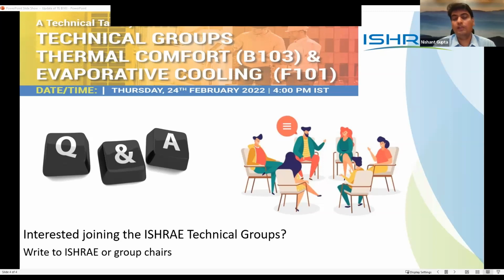Once you know that saturated effectiveness, you can anytime extract it from the psychrometric analysis. Rather, the recommendation is not to apply the effectiveness value taken from one manufacturer on another manufacturer's equipment. Absolutely. It will vary based on the face velocity across the pad, the type of pad that you're using, the media, the thickness. There are a lot of parameters, so it's better to take it from the OEM.